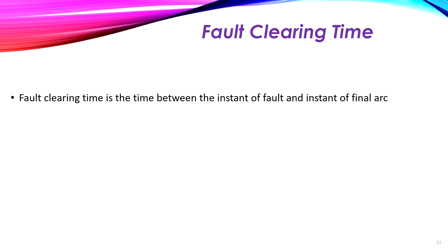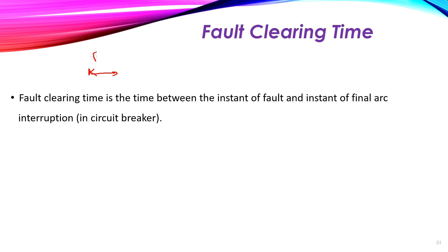The fault clearing time is the time between the instant of fault occurrence and the instant of final arc extinction or final arc interruption inside the circuit breaker. So the fault clearing time is the time of clearing the fault. At the first instant we have the fault occurrence, then after a certain amount of time — the relay time — which is the time taken by the relay to operate. For example, if it is a mechanical relay, the time it takes to close its contacts.